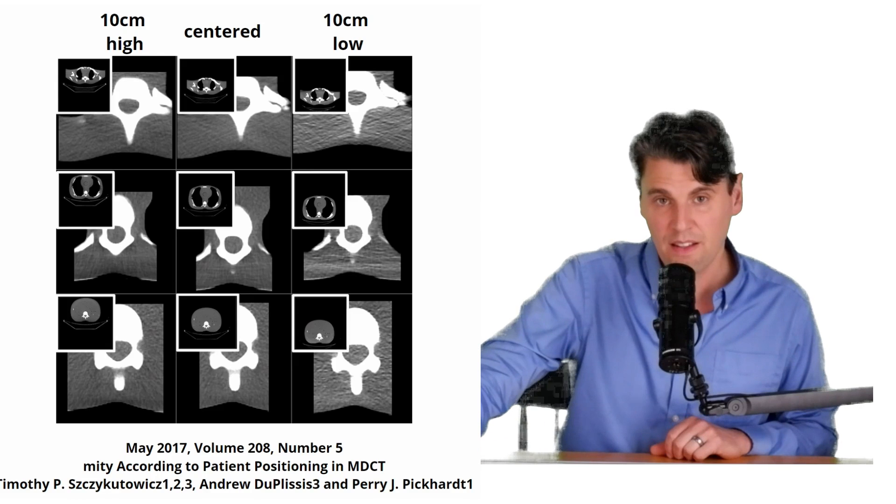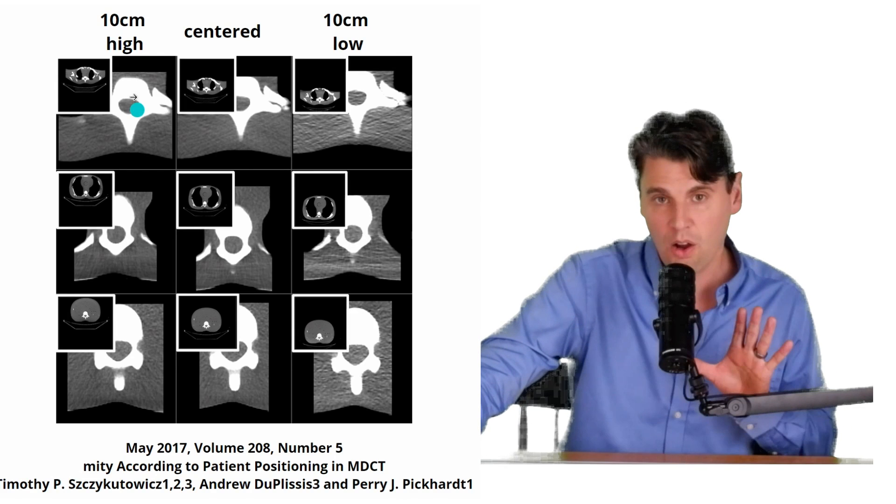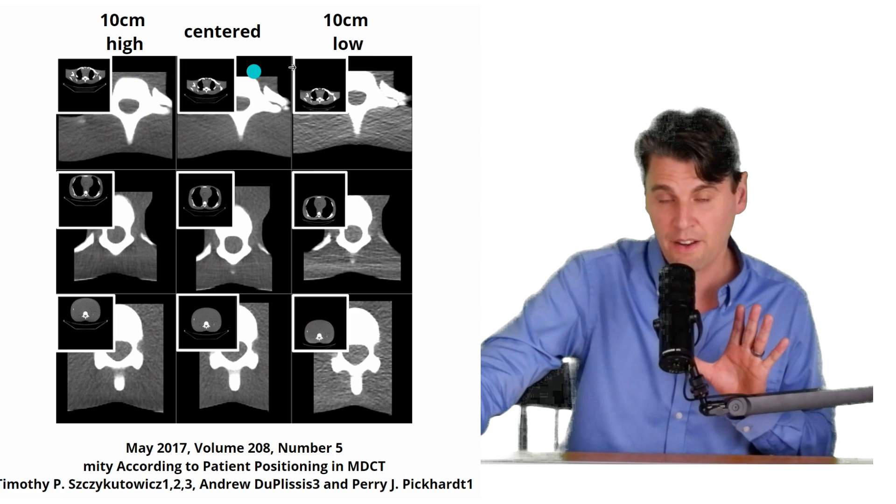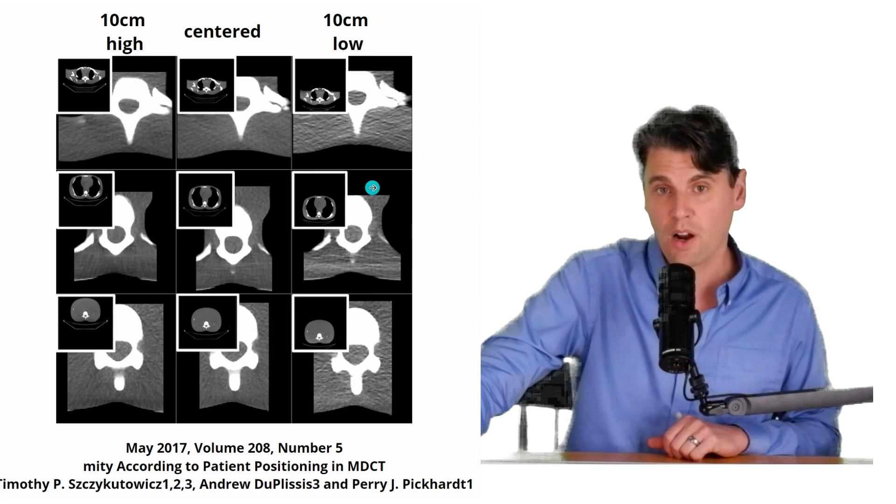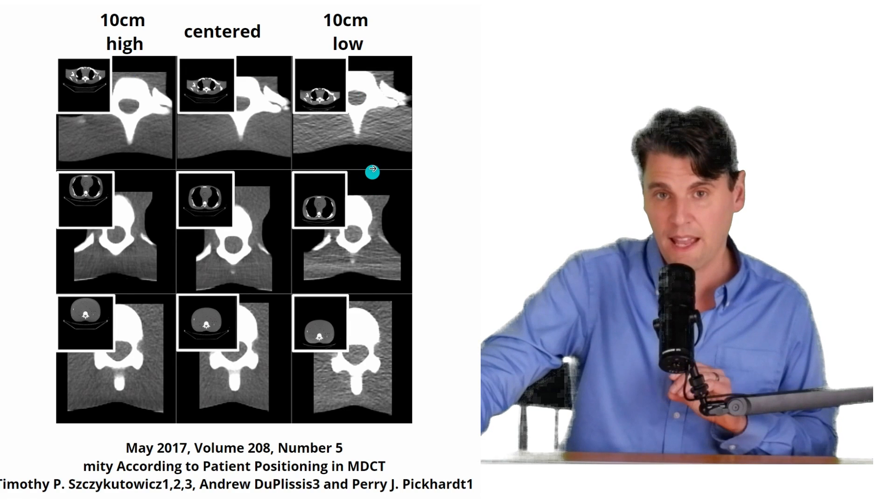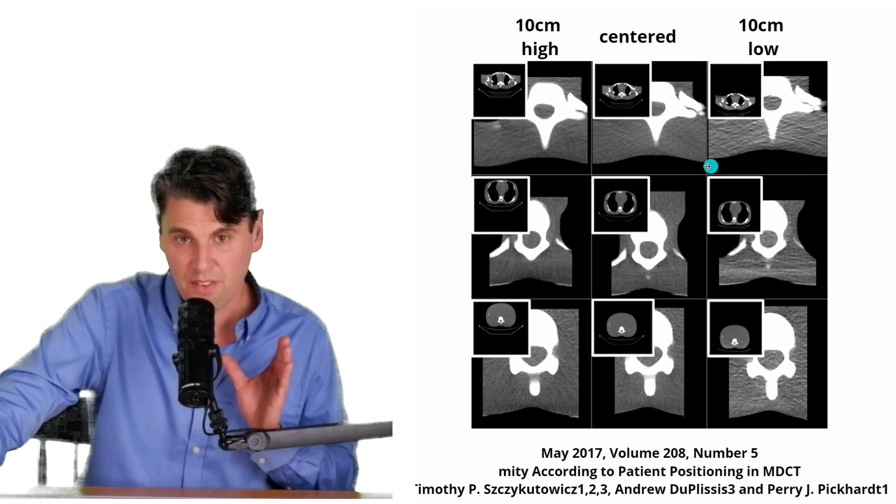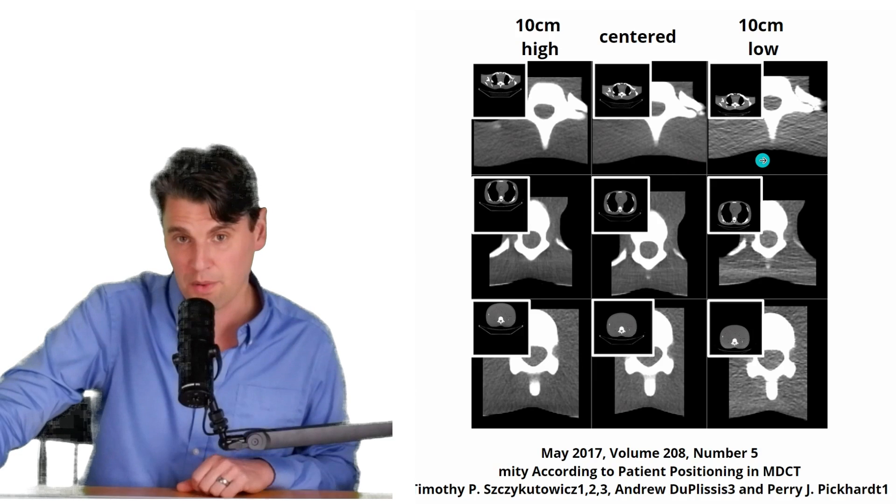And then a little bit later, Timothy Szczykutowicz at Madison did similar experiments showing even more extreme differences. In this scenario, the case where you're too high, where you're centered, and where you're too low, and for a region of interest that's around the spine, it's going to be really worse. There was a standard deviation that was double going from the center to the 10 centimeter too low acquisition.